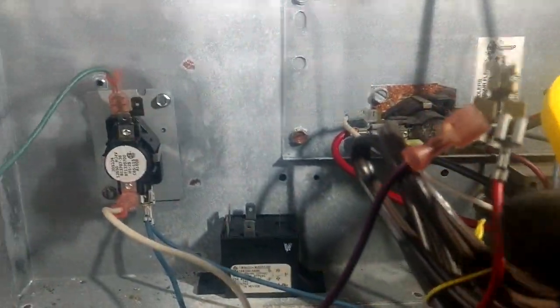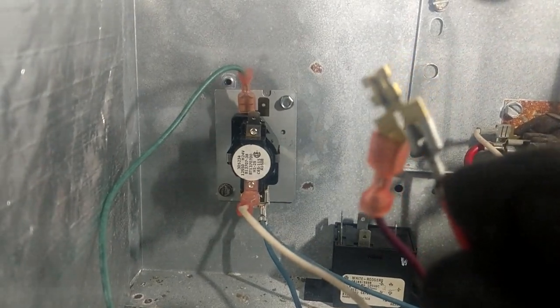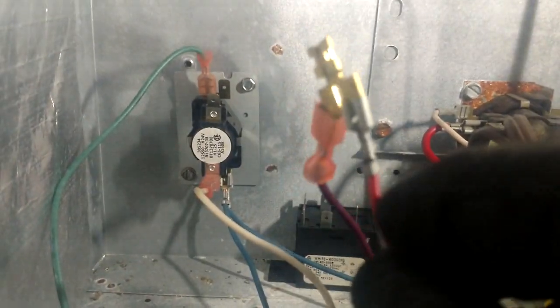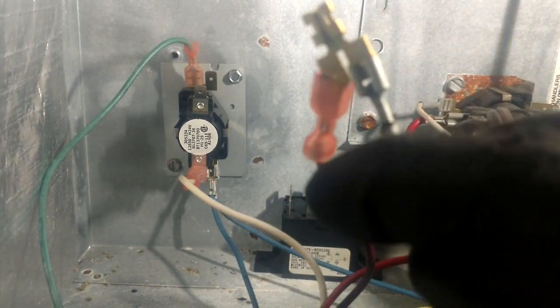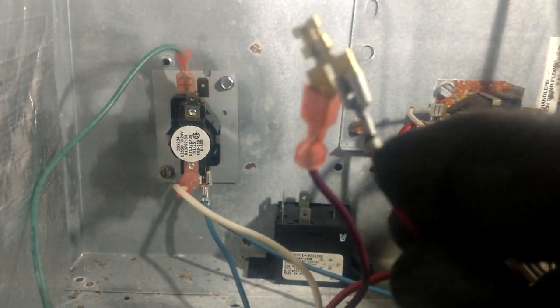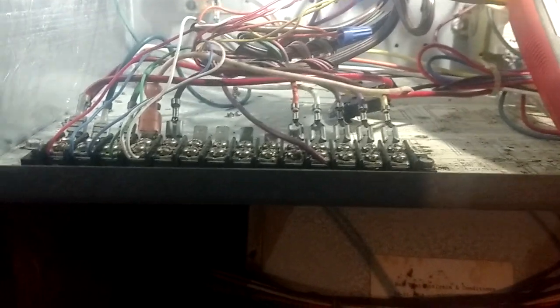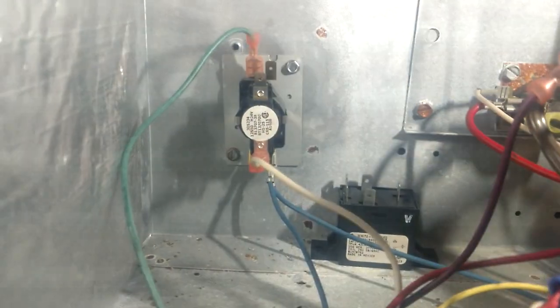Alright, you guys, so here we go. I've got one of these little double-ended stake-ons right here, and we have just jumped out our red wire to our purple wire, sending power down to the motor. And right now we still have no motor, so that's not looking too good. We might end up being a bad motor on this one. It would have been nice if it was just a relay and we could have got this thing up and going quickly, but we might end up having to do the blower motor on this one.